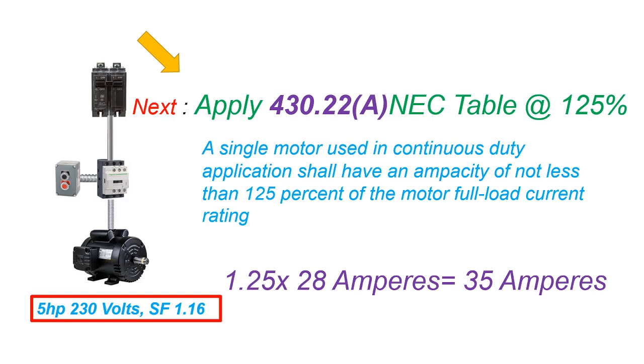Because it is a continuous duty motor — let's assume that unless it states something else, like an elevator which is intermittent duty — we're going to take 125 percent for sizing this branch circuit conductor, as per NEC 430.22(A). That gives us 1.25 times 28 amperes, which equals 35 amperes.